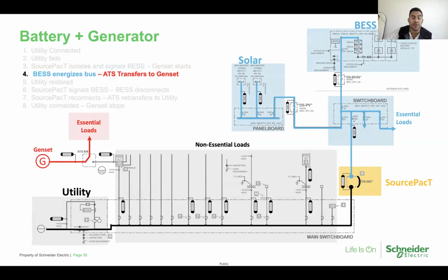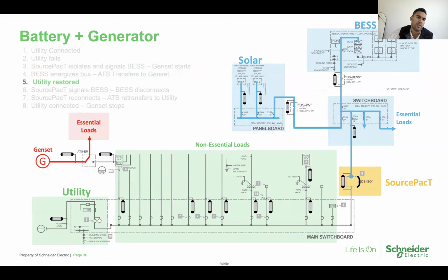Now your emergency loads, NEC 700 loads, are on the generator, and your optional standby loads are on emergency power provided by the energy storage system. And of course, when utility is restored, both the ATS and SourcePacT operate as specified. They will remain isolated in this situation where the ATS is connected to source 2. SourcePacT will keep the motorized breaker open. We'll send another signal to the BESS to shut down.